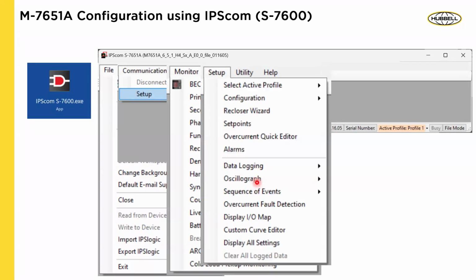Then you have setup. This is where most of your settings come in. Set points is where you configure most of your settings, and configuration is where you set the relay settings, right? So if there's device-specific things, you set them there. And then we also give you a wizard, right? There's a wizard for reclosing that you can go in and program a certain function without going into individual elements and programming them one by one.